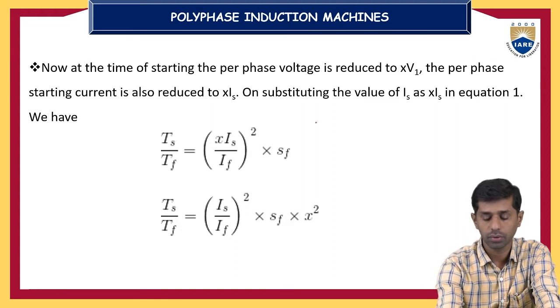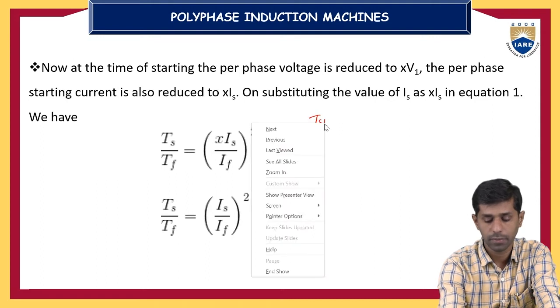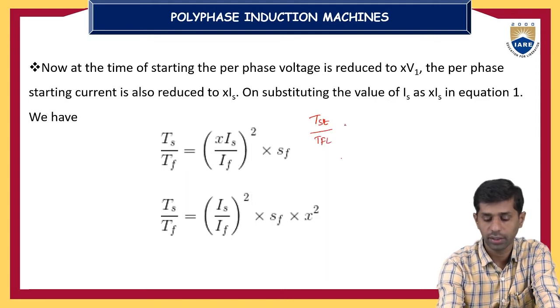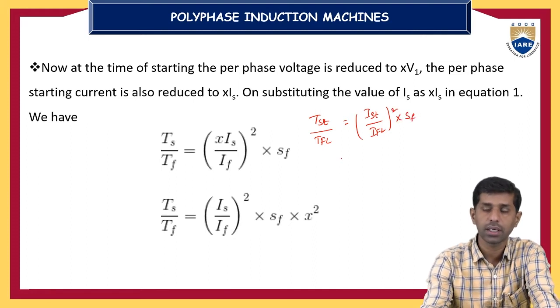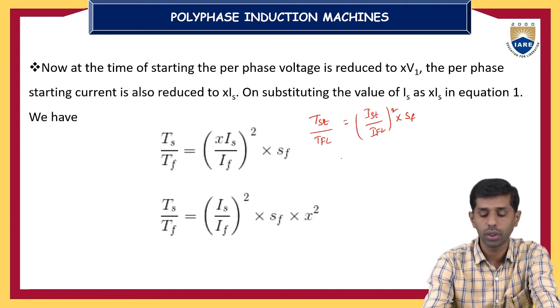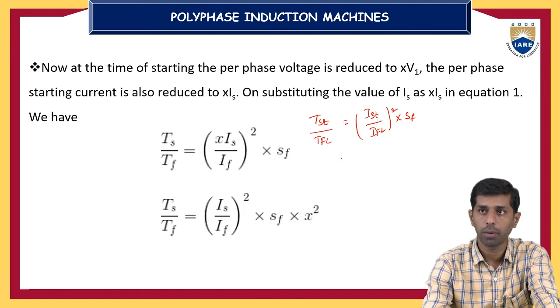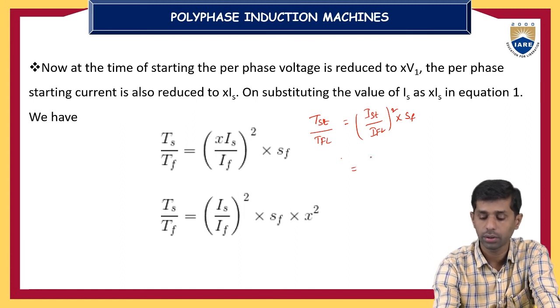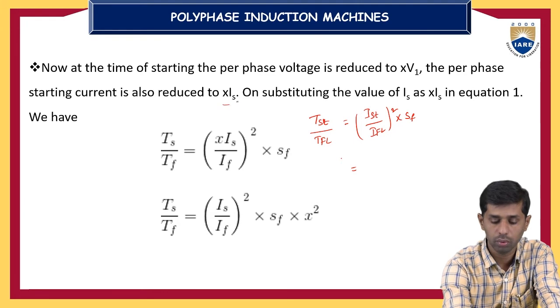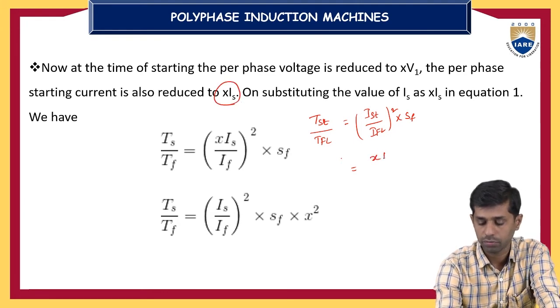So we can derive the expression as in the previous case. T_ST by T_FL equals the general expression: current at starting by current at full load, whole square, into slip at full load condition. But because the resistors are connected in series with each phase, the voltage drop is some fraction of the applied voltage, that is x times the applied voltage. Similarly, it also reduces the current to x fraction. So x times the starting current is the current because of the starting resistor method, into slip at full load.